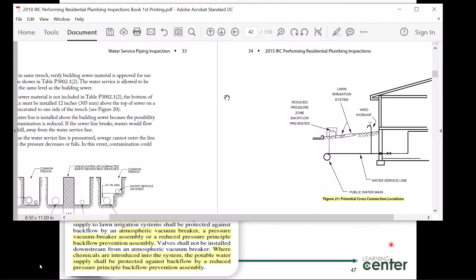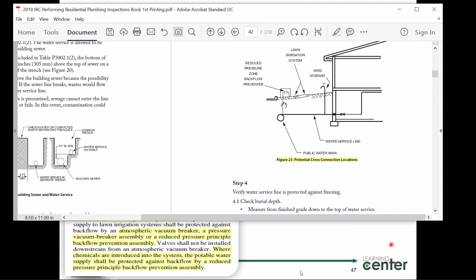Now, here's how this works. I'm going to show you what's called a pressure vacuum breaker, all right? Let me go back and show you our application. Open your workbook, ladies and gentlemen. Here's your workbook right here. If you open your workbook, you're going to go to this graphic right here. You with me? Does everybody have this open? This graphic right here, okay? I'm going to come in with my water supply into the bottom of this backflow preventer. So in other words, I'm going to pipe in from the bottom, okay? So when I pipe in from the bottom, I'm coming right into this particular port right here to the inlet of the pressure vacuum breaker.